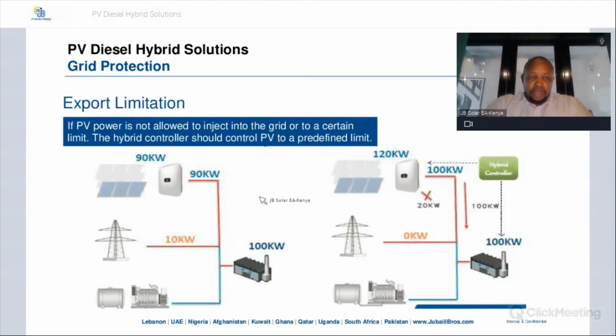And you can see here we have, again, a load of 100 kilowatts. We have the PV array of 90 kilowatts, and 10 kilowatts coming from the grid. So when you have more generation coming from the PV than what is required by the load, the excess won't be fed into the grid. And this is where the hybrid controller sets this limit or acts as zero feeding into the grid. So you have, again, grid protection.